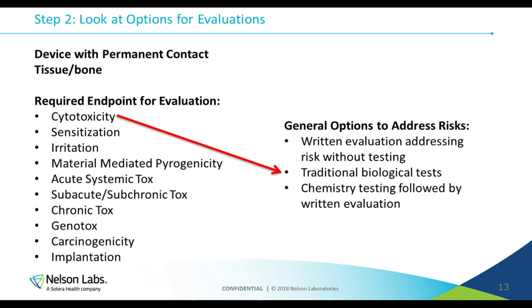So here you can see on the left-hand side of the slide is a list of all the required endpoints for evaluation for this device. And then on the right-hand side, there's a list of the general options available to address risk. So like I said, one way or another, they all have to be addressed. And usually you can either write an evaluation without doing any testing at all, or you could do a traditional biocompatibility test, or you could do chemistry followed by a different type of written evaluation.